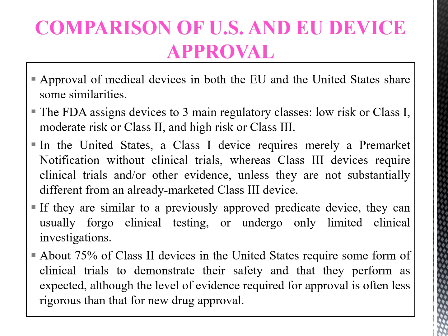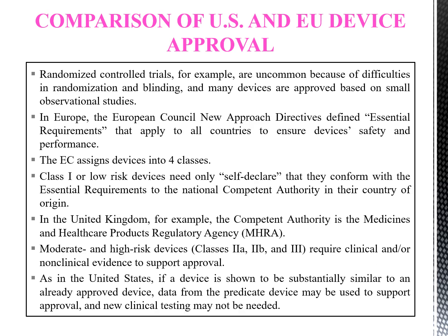A predicate device is a previously approved device that is considered as a control. If a new device is similar to a previously approved predicate device, it can usually forego clinical testing or undergo only limited clinical investigations. About 75% of Class 2 devices in the United States require some form of clinical trials to demonstrate their safety and that they perform as expected. Although the level of evidence required for approval is often less rigorous than for a new drug approval, randomized controlled trials, for example, are very uncommon because of the difficulties in randomization and blinding. Many devices are approved based upon small observational studies.